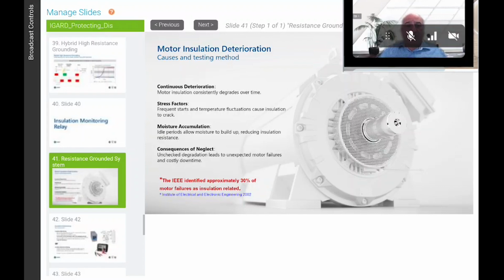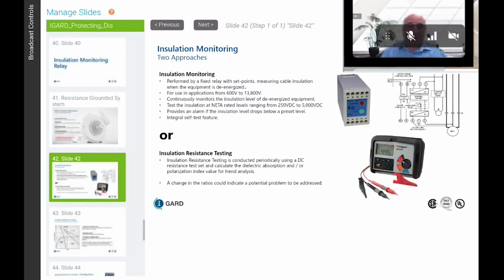So we're also coming up with motor insulation deterioration or motor protection relays, looking at the insulation of a motor before you turn it on. There's continuous deterioration of a motor, there are stress factors, moisture, consequences of neglect. When you shut off a motor that's been running for a long time, it's hot, it's going to accumulate dust, it's going to accumulate moisture. Before you turn it back on, you want to make sure that the motor has good insulation with respect to ground, and that's what this insulation monitor does.